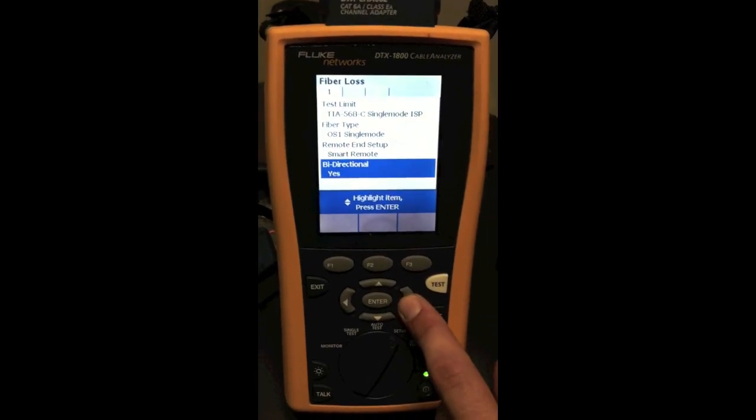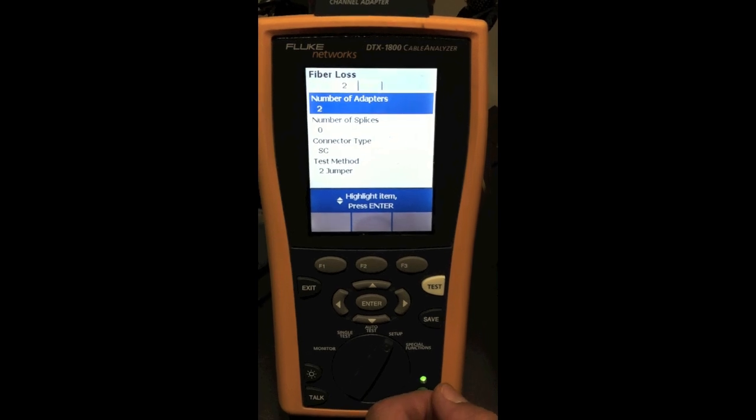Other things in this setup that you want to check for are under tab 2 which you can get access by scrolling over and the number of adapters that we have here. This comes into play when we're testing through multiple patch panels that we have more than one adapter that we're testing through. This would allow the unit to not confuse the data as it comes back to the tester. Number of splices. If you have splices in the section of cable that you're testing you want to also input this number into the unit so it can compensate for the amount of loss of the splice.